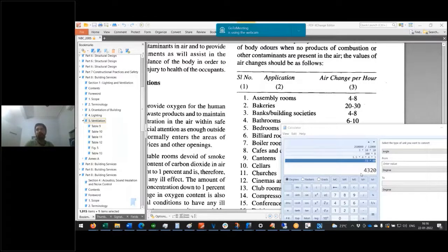Okay, fine. Sir, if I put any timers or controls for these fans, do we have to add any allowance to this CMH which we calculated, 4,320? If I am having an energy management system or timers for energy efficient operation of these fans, suppose I am putting a VFD, will that affect this value? Yes, absolutely. What you can do is connect it to a CO2 sensor, which will detect the number of people. If there are fewer people, you can save energy. Put a VFD on the fans accordingly. Okay, so during the design stage, we have to select the maximum value.